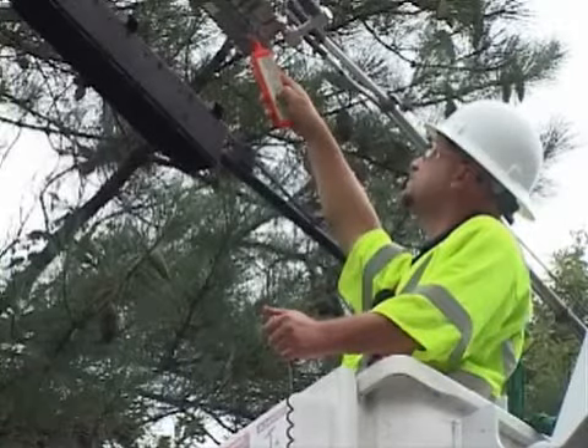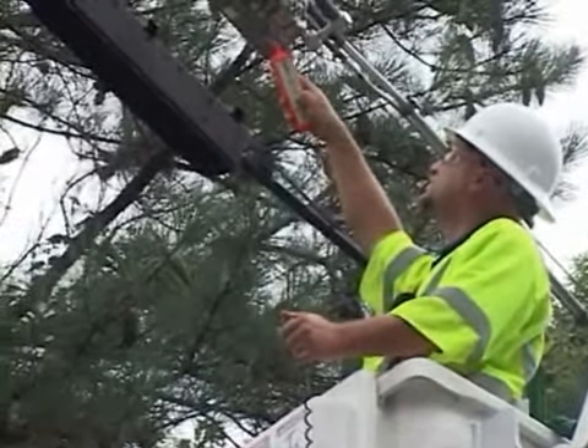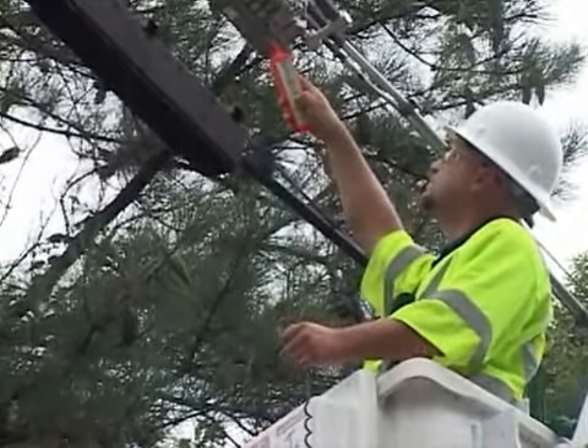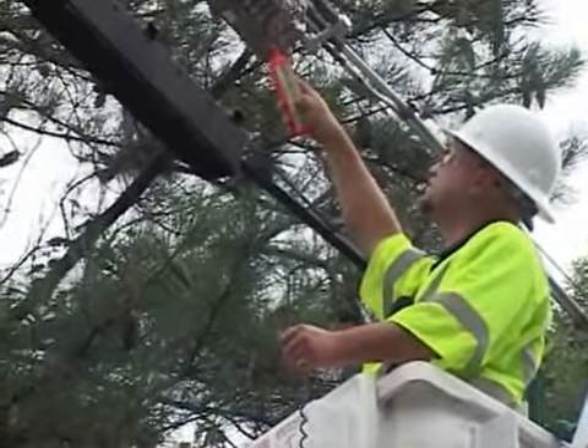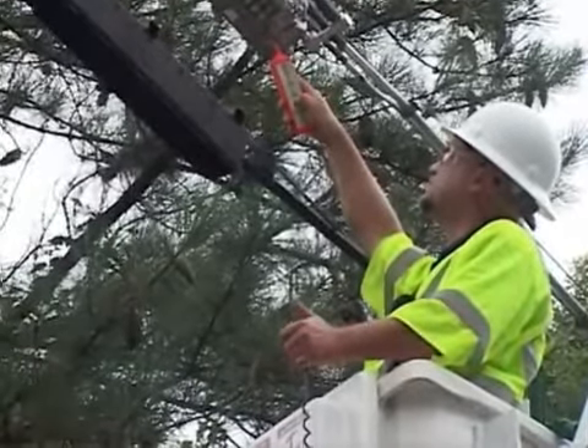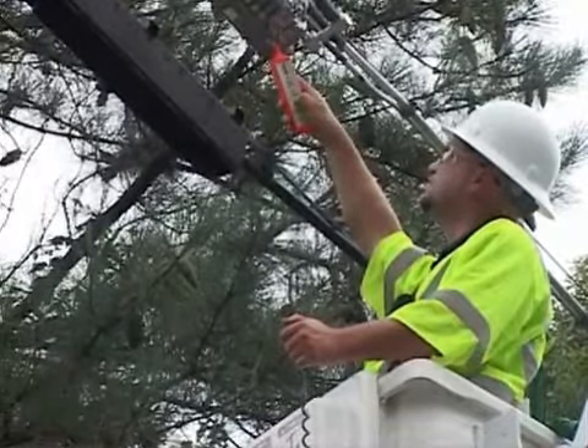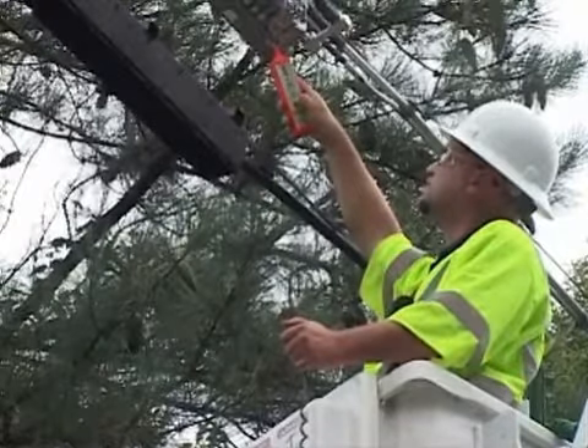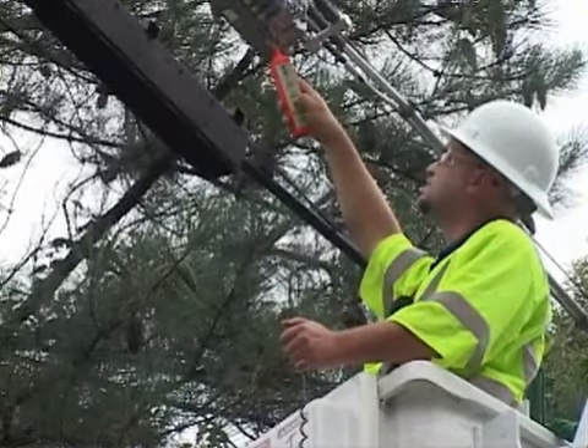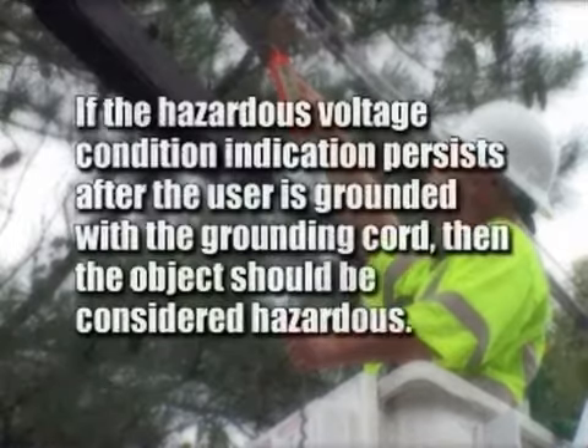Notice when the operator grounds himself, the object ceases to indicate a hazard. When the ground cord is released, the voltage is again detected. If the hazardous voltage indication disappears, the user was energized and must continue to keep himself grounded while testing with the FVD. If the hazardous voltage indication persists after the user is grounded with the grounding cord, then the object should be considered hazardous.